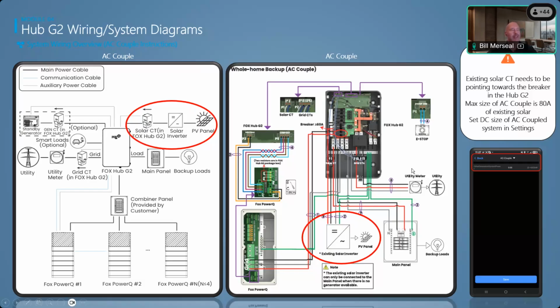So if we're doing an AC system, there is what they call a solar or an AC breaker. If you're used to installing an Enphase system where there's a gateway, once the combiner goes into that gateway, all your micros go into that gateway, it goes to a breaker into your main panel. Instead of that breaker going into the main panel, it would actually go into the hub. The reason that's super important is because we need to be able to control that solar system.